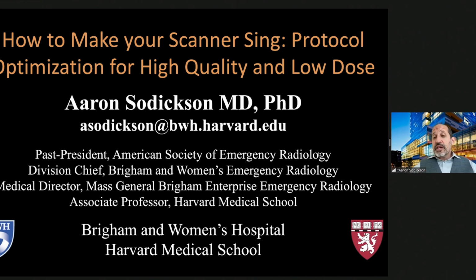But I'll tell you that we actually configured our scanners to only allow 100 or 120 kV, at least for our vascular scans. 140 kV we don't like for our vasculature because you throw away your Hounsfield units. Yes, you get better penetration of the larger patients, but at the expense of losing your enhancement from iodine, which is the point of the scan. So for us, we always limited that to either 100 or 120.